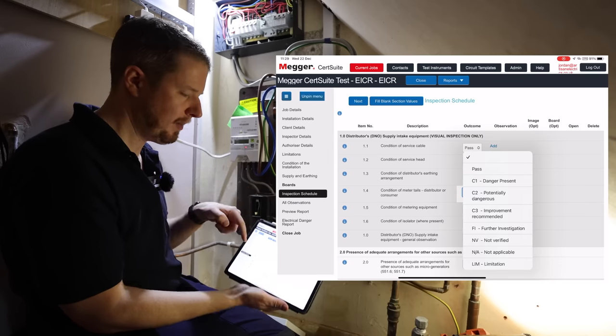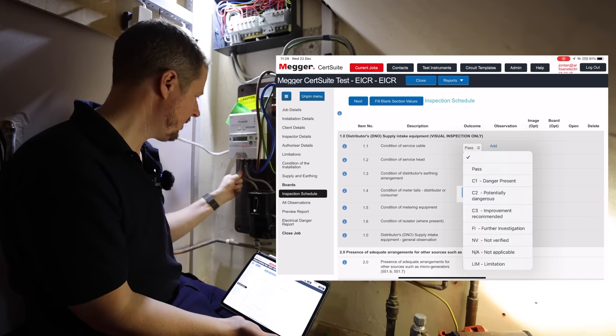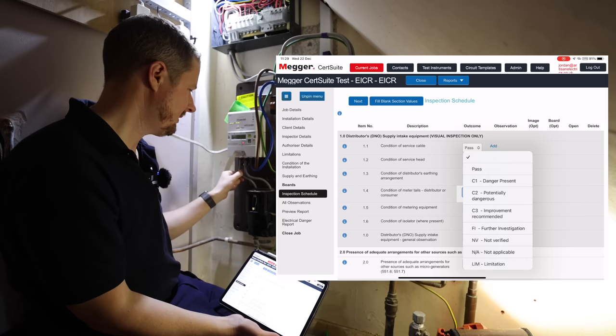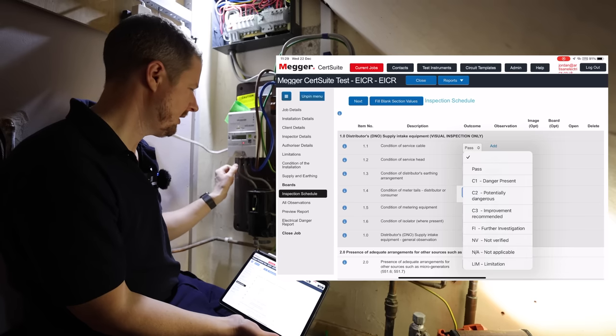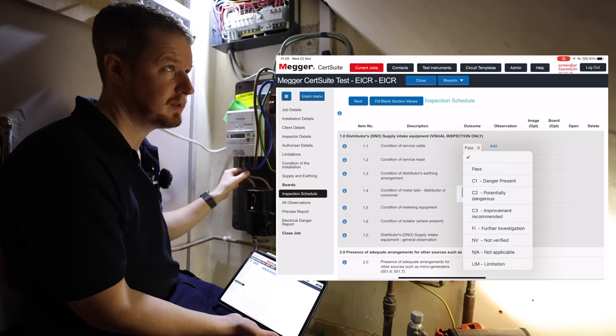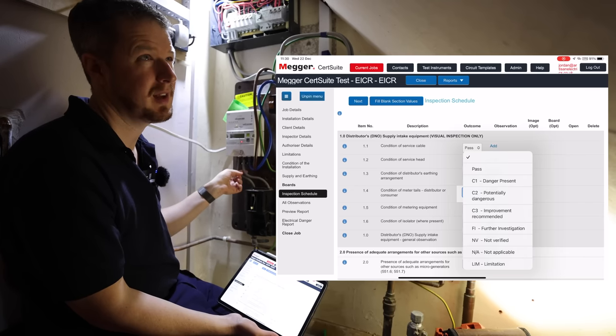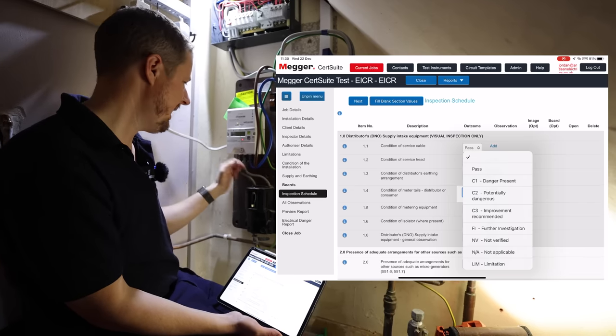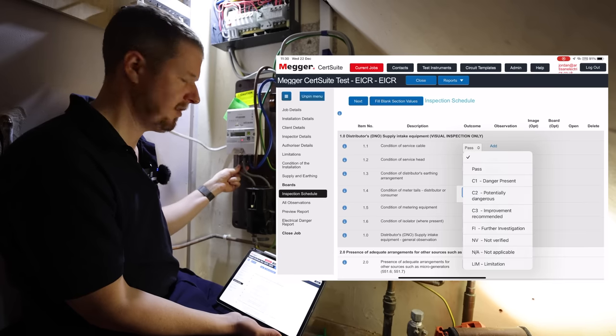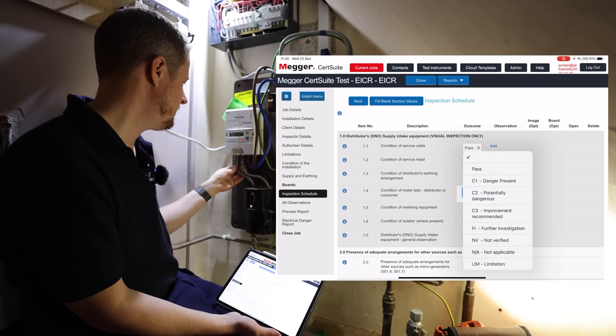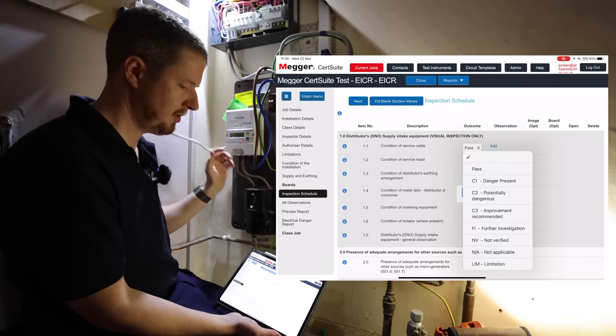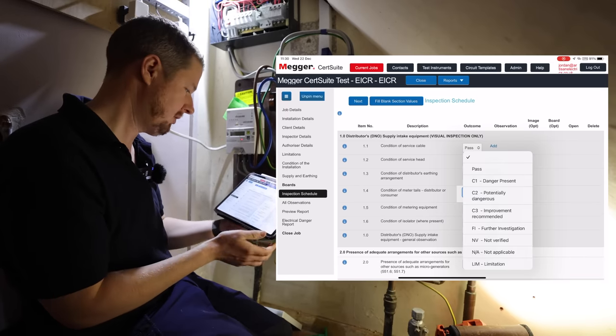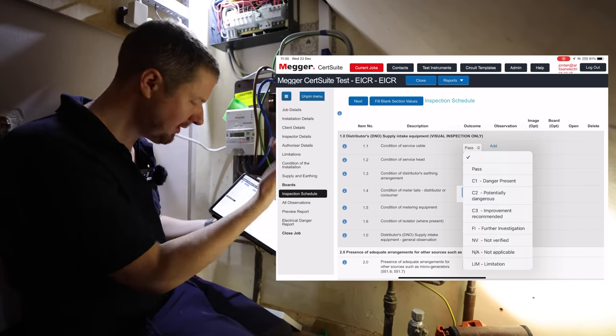Now let me know in the comments, guys, if you do EICRs, do you code the fact that you've got 16mm cable meter tails? Because I know in the ESQCR regulations, the Electrical Safety Quality and Continuity Regulations, now it says that you should actually have 25mm tails as standard for every installation, but some people choose to code that as a C3, other people don't. Let me know in the comments.